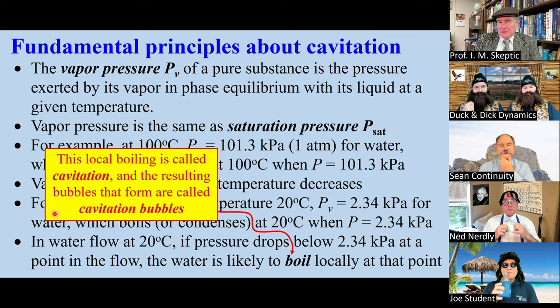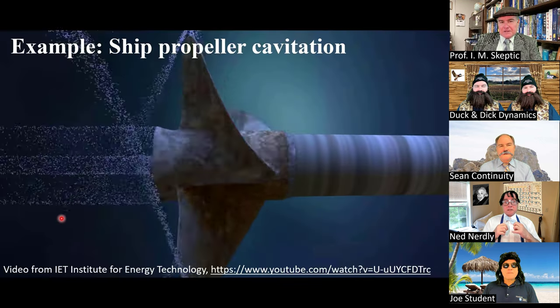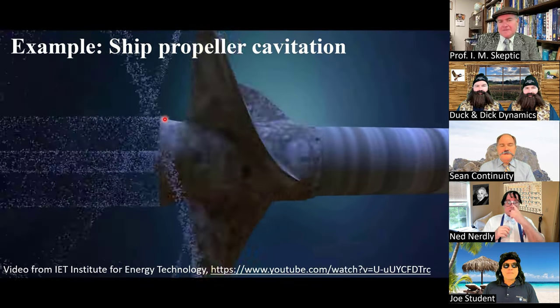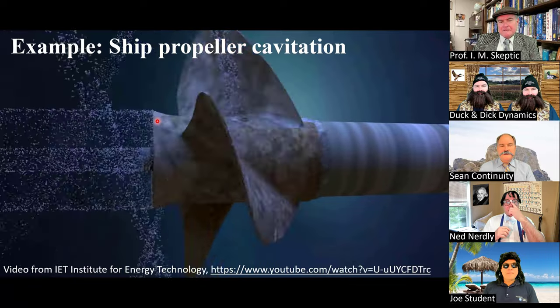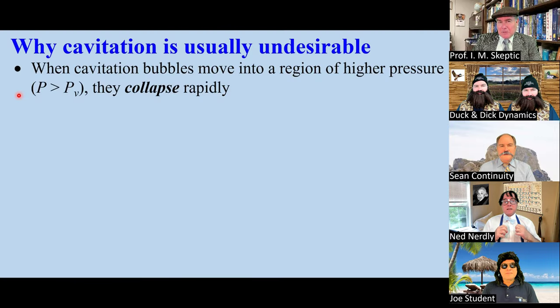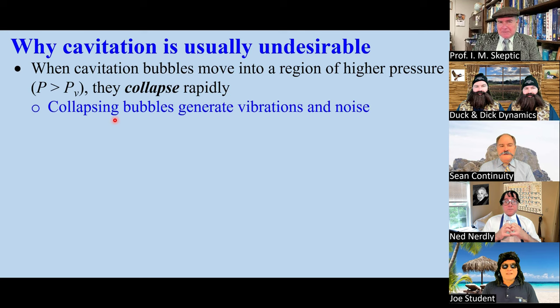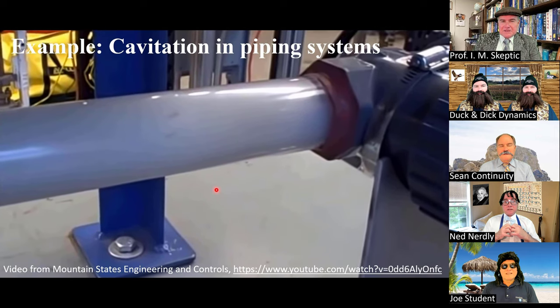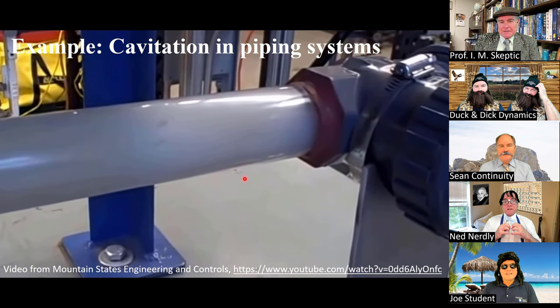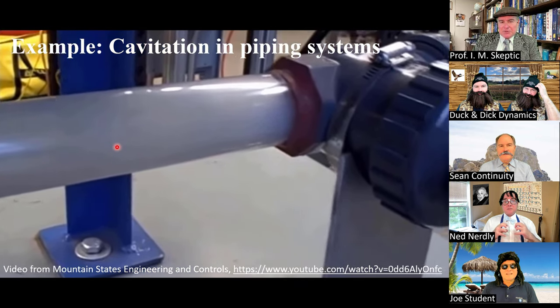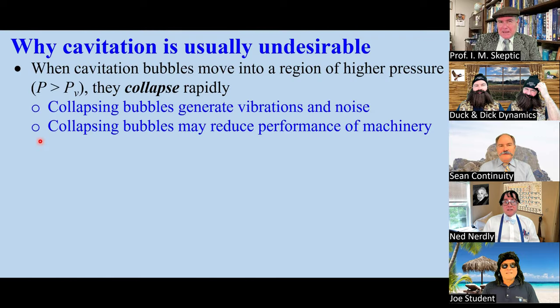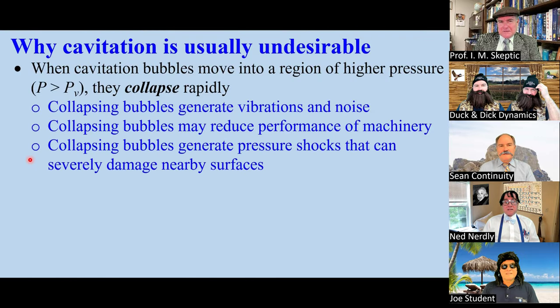The bubbles that are formed are called cavitation bubbles. Here's an example of ship propeller cavitation. Cavitation is usually undesirable because when these bubbles move into a region of higher pressure, they collapse rapidly. These collapsing bubbles generate vibrations and noise. Here's an example of cavitation in a pipe — you can both see the bubbles and hear them. These collapsing bubbles may reduce performance and can severely damage nearby surfaces.